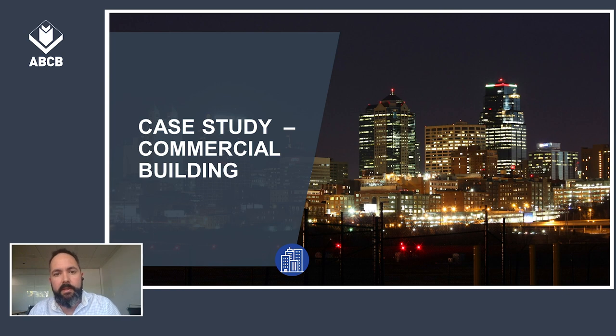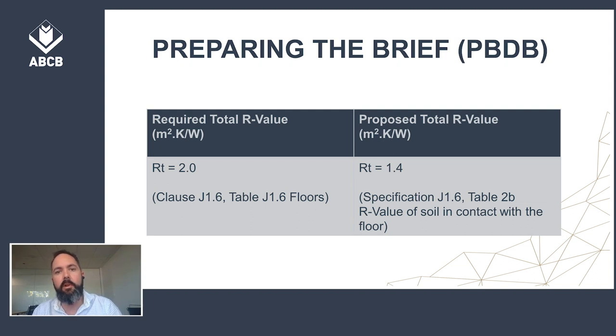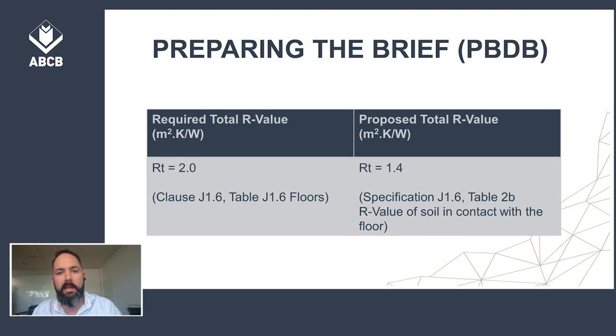Let's now apply this to a case study. We'll be using a simple petrol station in South Australia, NCC Climate Zone 5. The consultant group undertook a Section J review of the design of the proposed petrol station. An initial deemed-to-satisfy assessment deemed the floor as non-compliant with J1.6 floors. The required total R-value of the floor to comply is 2.